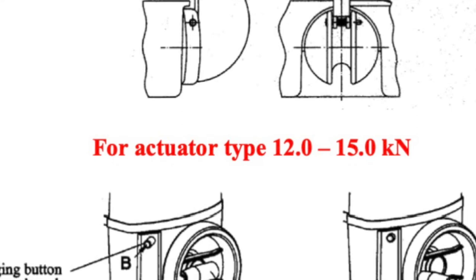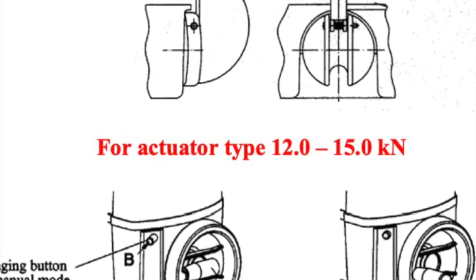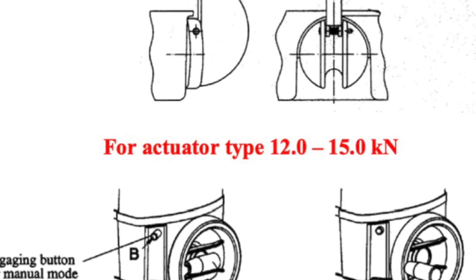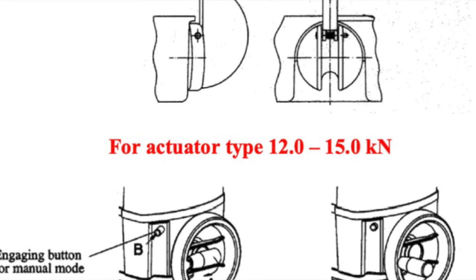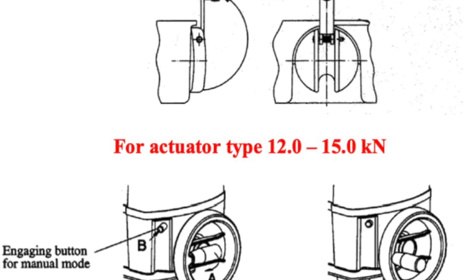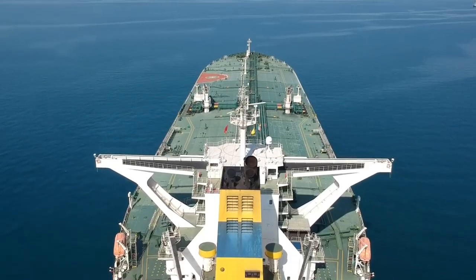I would also like to inform you that there are different types of actuators, and depending on the type of actuator there is a different engaging system. For actuator types 2.2 to 5 kN it is not necessary to engage any button. On the other hand, for actuators from 12 to 15 kN there is an engaging button for manual mode. Please verify that there is no power supply provided to these actuators, as damage to the gearing system can be done.